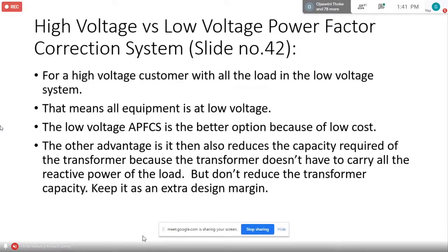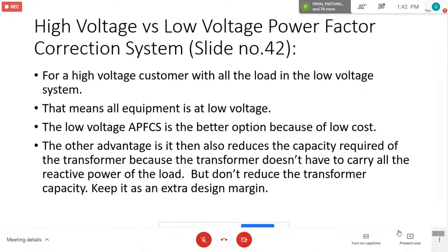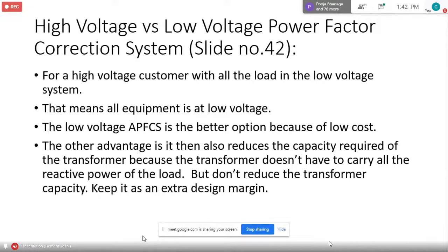Okay, so for example, you are receiving power at high voltage because the power company says your total demand is more than a certain kVA, so we are going to give you HV supply. Then you get HV supply and you step down, and all your load is at low voltage. So in this case, you are better off putting in the low voltage system. The other advantage is that it also reduces the capacity required of the transformer, because the transformer doesn't have to carry all the reactive power of the load. So closer to the load, better. But it doesn't work out practical. Don't reduce the transformer capacity, keep it as an extra design margin.